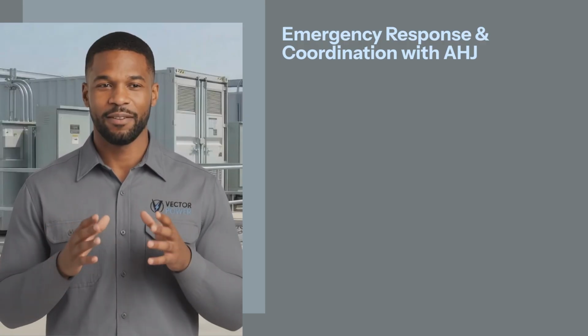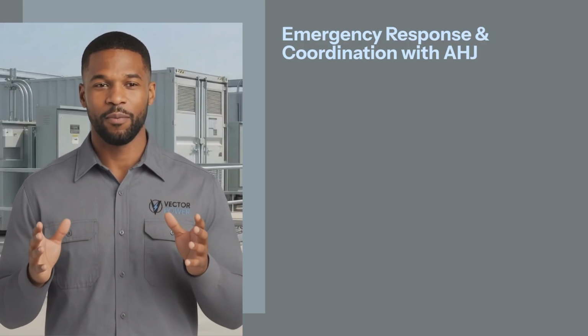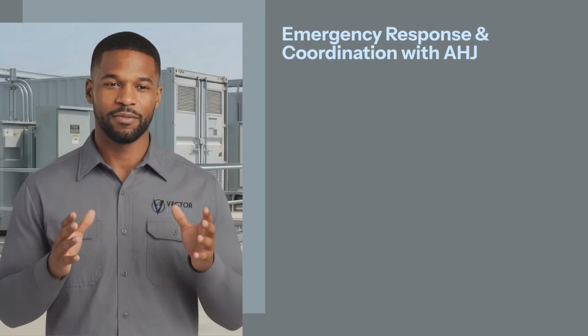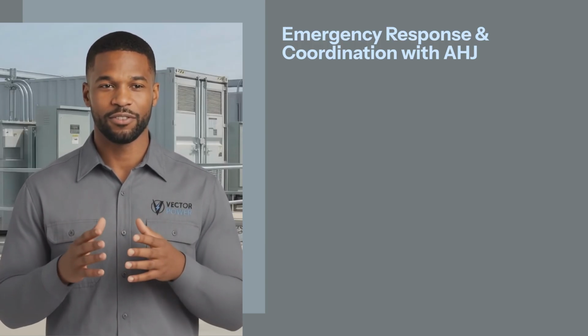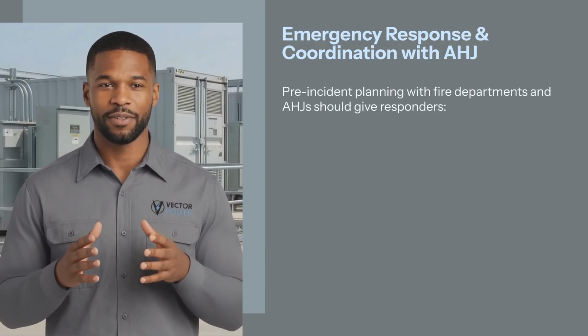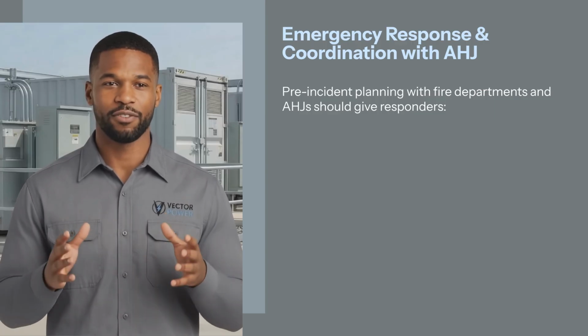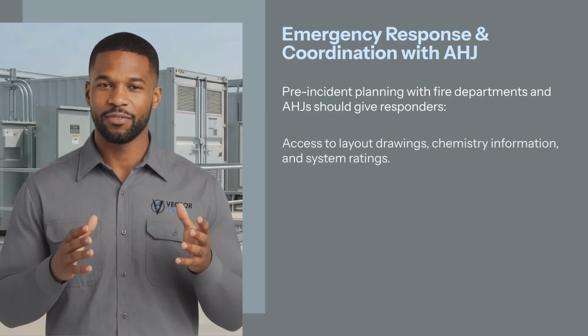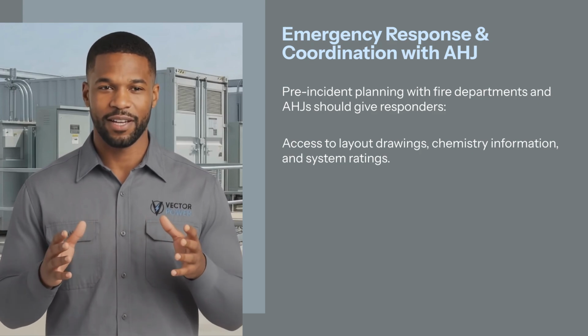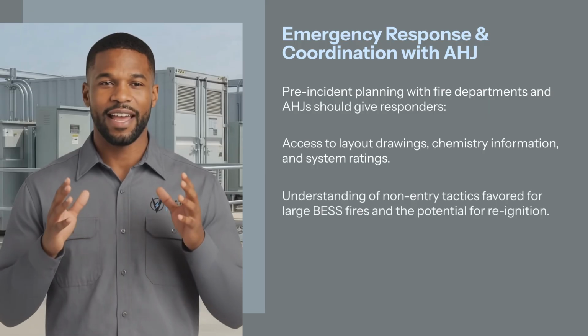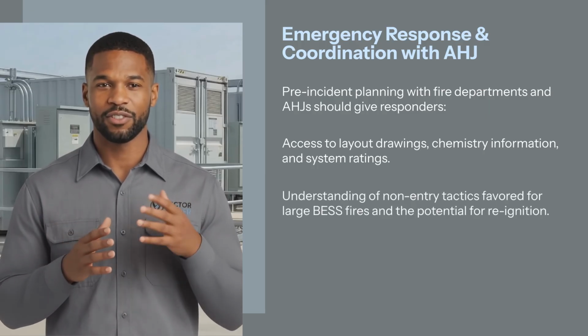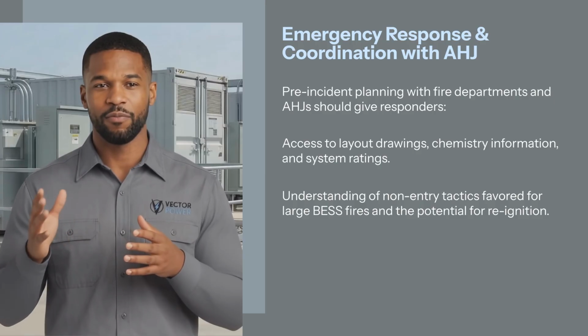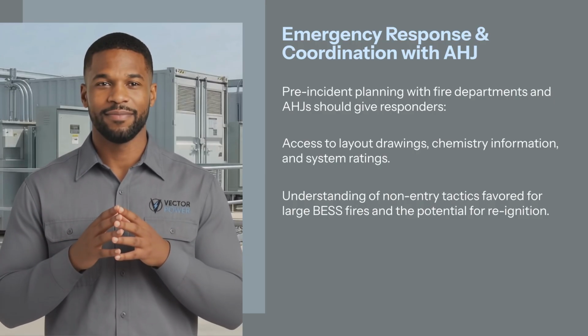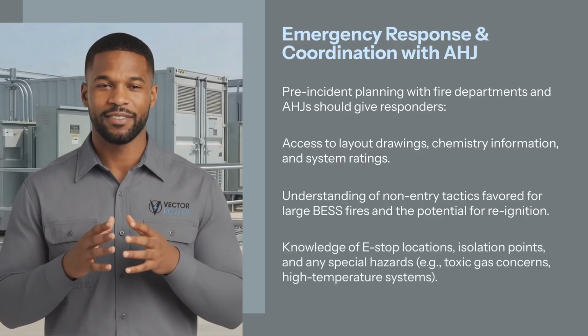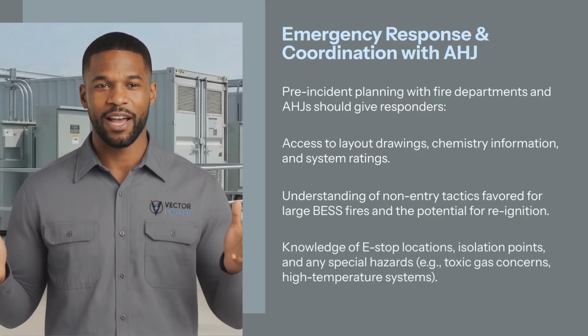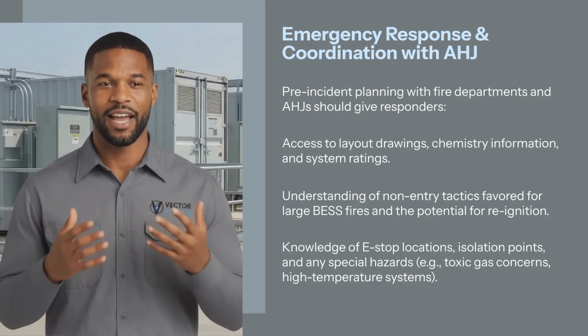Finally, the last area that we will cover under the topic of fire, thermal runaway, and system safety will be emergency response and coordination with the authority having jurisdiction. Pre-incident planning with fire departments and the authority having jurisdiction should give responders access to layout drawings, chemistry information, and system ratings; understanding of non-entry tactics favored for large battery energy storage system fires and the potential for reignition; and knowledge of e-stop locations, isolation points, and any special hazards, for example, toxic gas concerns in high-temperature systems.